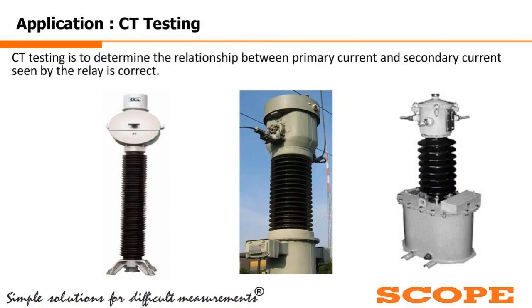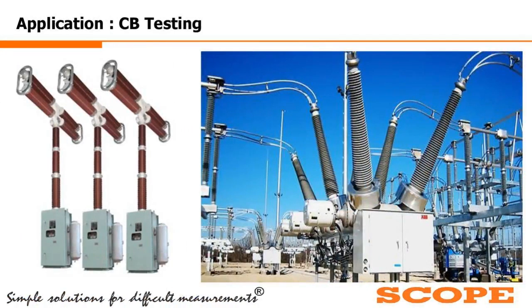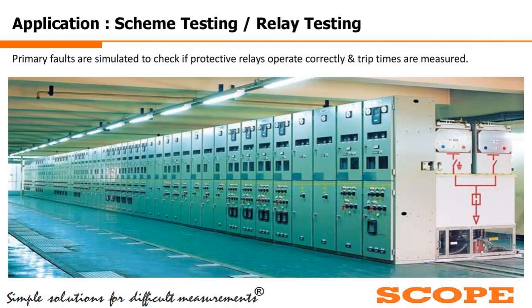The applications of the primary current injection test set: first is CT testing — with the primary current injection test we can test a CT to determine whether the relationship between primary current and secondary current seen by the relay is correct or not. The second application is CB testing — we can directly inject rated current through the circuit breaker and check the CB behavior: whether it trips beyond the rated current limit.